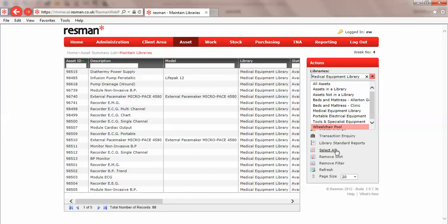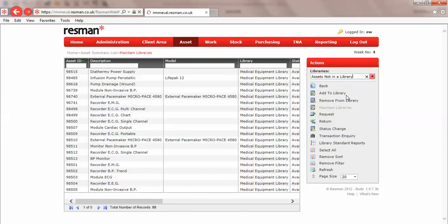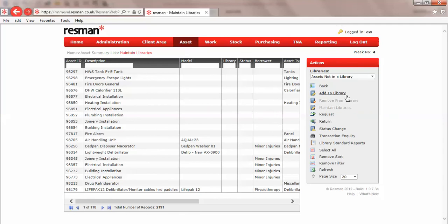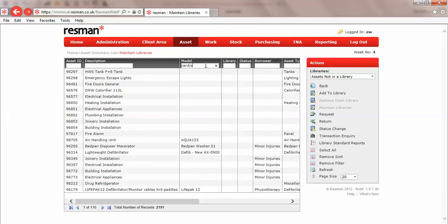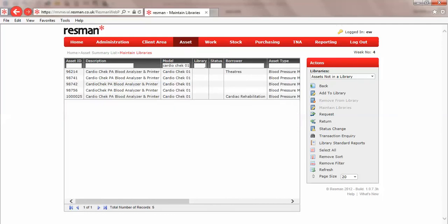So I'm going to choose assets not in the library, and we know that what we'd like to add in now to our medical equipment library is some Cardio Chek blood analyzers. If I go into the model field in the filter row and type in Cardio Chek 01, that finds five items.